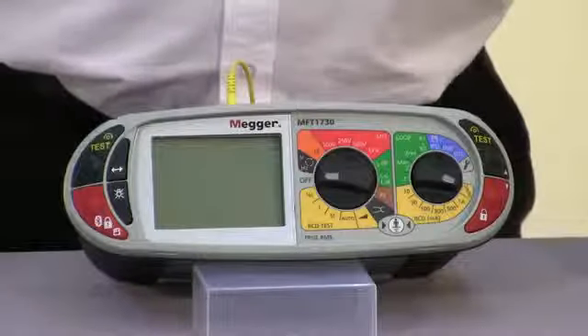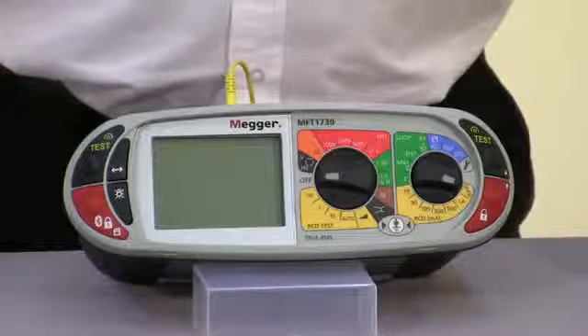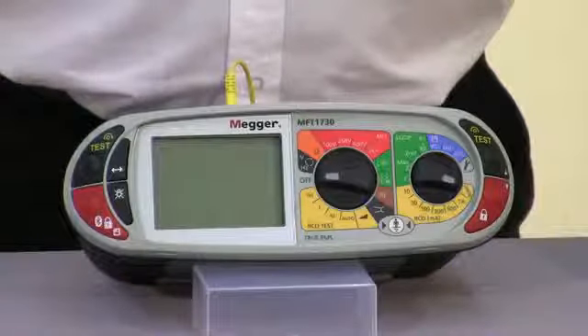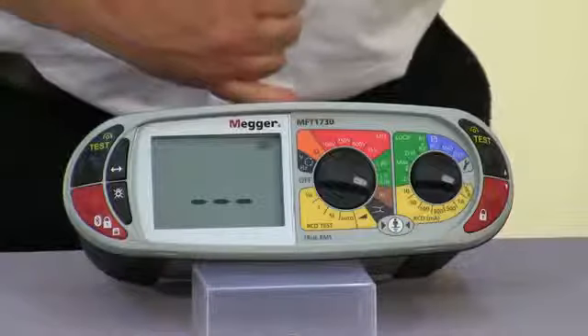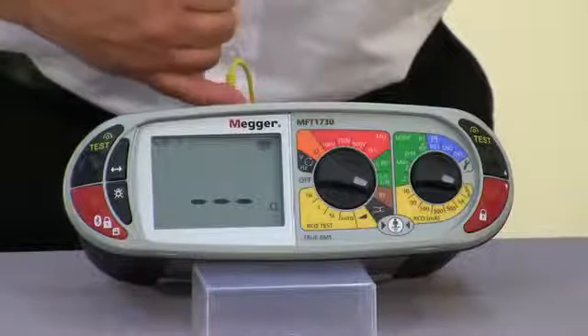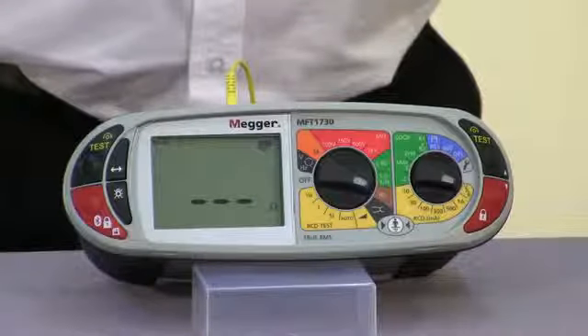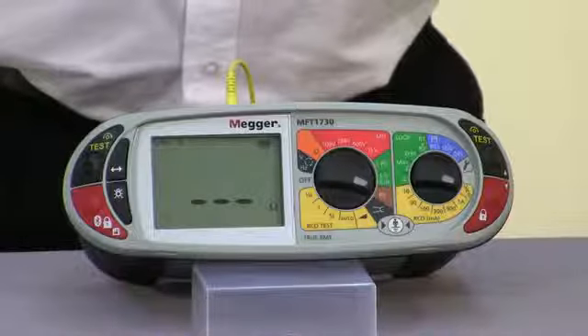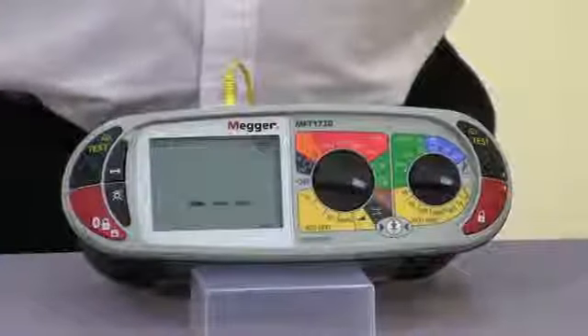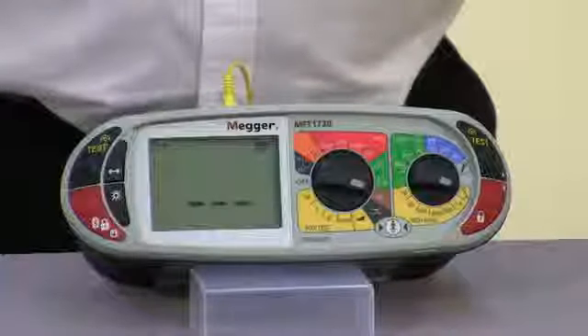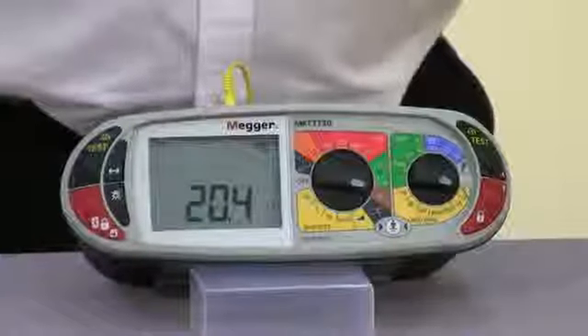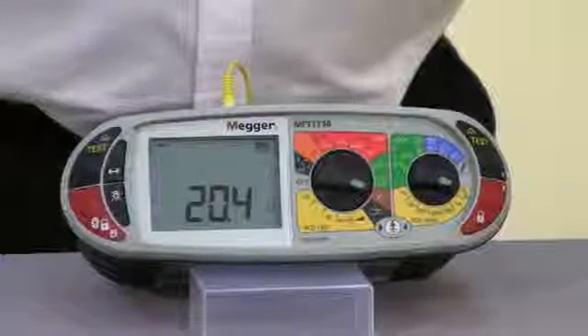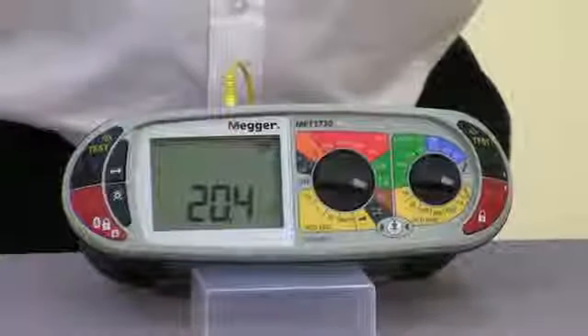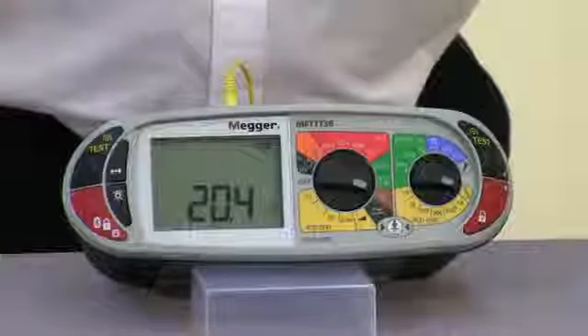The final test we'll look at is available only on the MFT1730, and that's our 3-wire ground stake or earth resistance test. So as you can see we've got our RE test range. Now in the top of the unit I've got a standard 3-wire ground stake simulator connected via the 3 wires. So we have our earth rod on the green, our potential probe on the yellow, and our current probe on the red. So initiating the test sequence, one of the nice things about the MFT1730 and this ground resistance test is that in the event of having a high P2 or C2 measurement, the unit will come back and indicate that for you. So as you can see on the simulated earth we've got a reading of 20.4 ohms.